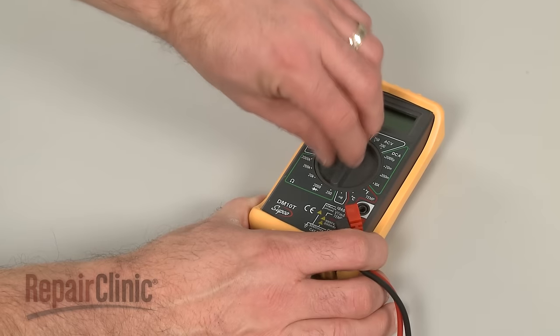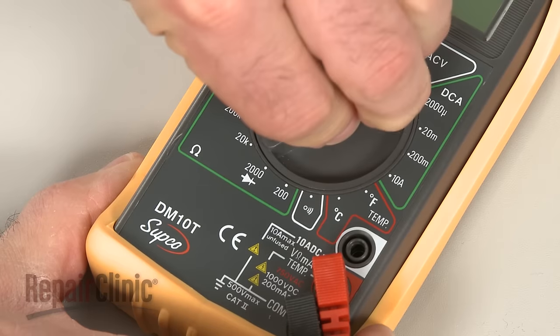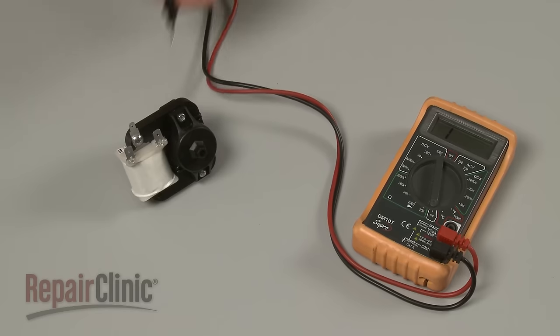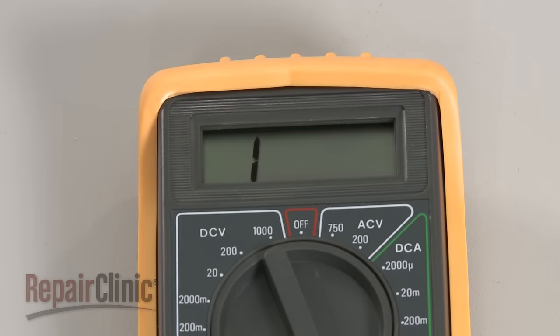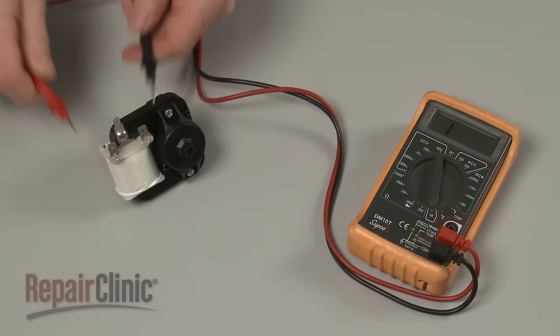You can also use a multimeter to test the motor windings for continuity, a continuous electrical path present in the motor. If the motor tests negative for continuity, then the component has failed electrically.